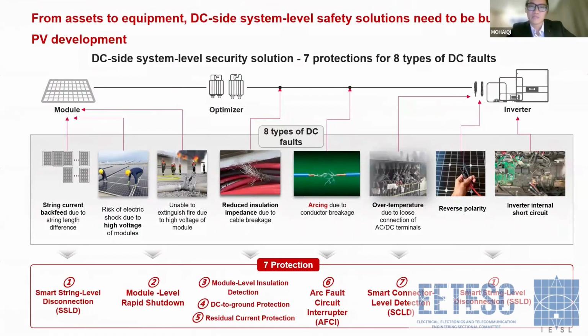So the first type of DC fault is reduced insulation impedance. And the next is about arcing. I think arcing is the main topic we're going to discuss today. And sixth is regarding over temperature. If poor quality equipment is used when doing the cable connection, the connectivity will not be proper. So there will be some arcing, and then the temperature will increase. It can also cause some damage to the inverter.